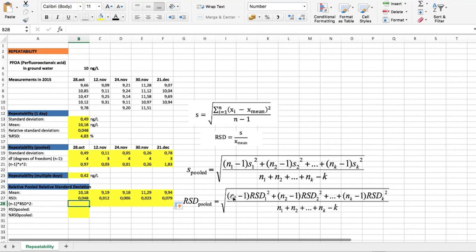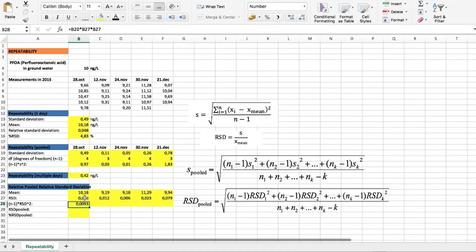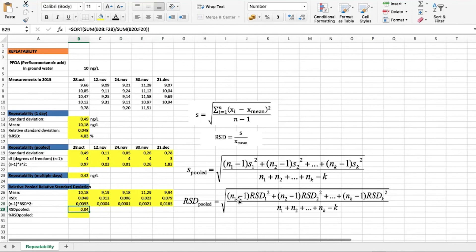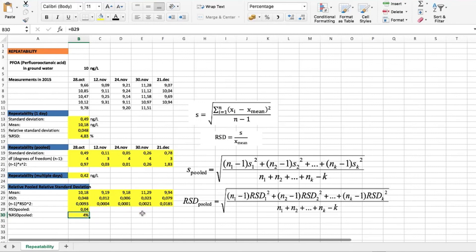We then find the parts of the formula using the degrees of freedom and the relative standard deviations for each day. Using this formula, we calculate the relative pooled standard deviation and, similarly to before, express it as a percentage for a clearer interpretation of our repeatability evaluation. The result is 4.1%. This was the calculation to find repeatability during your validation studies.